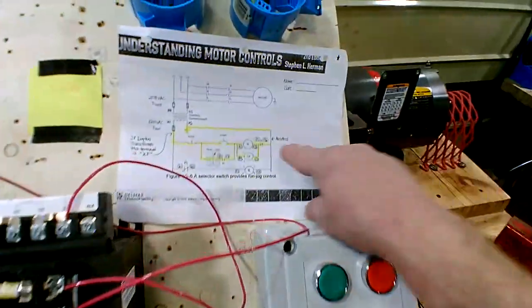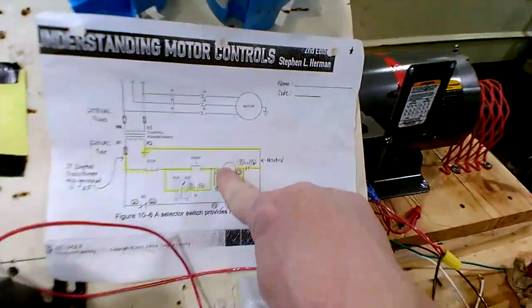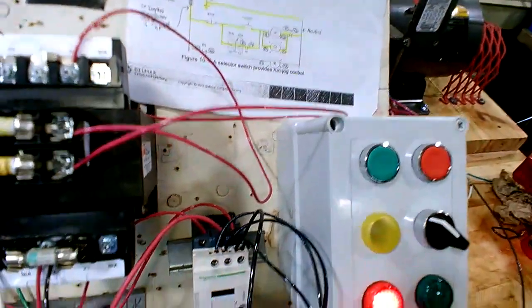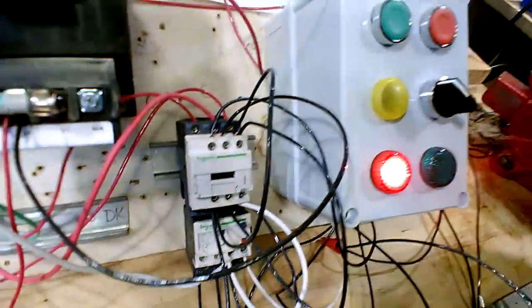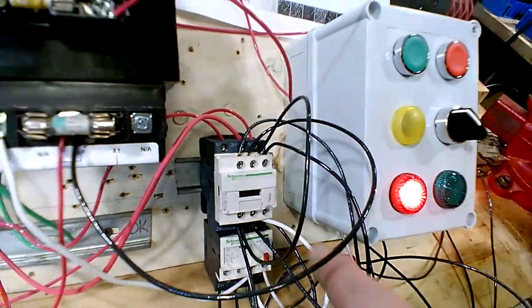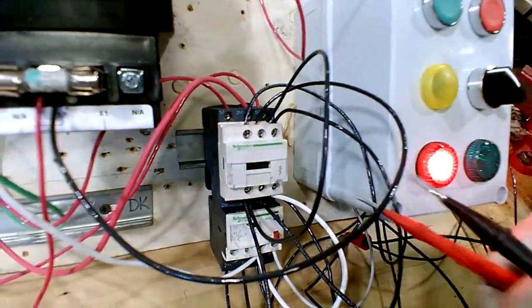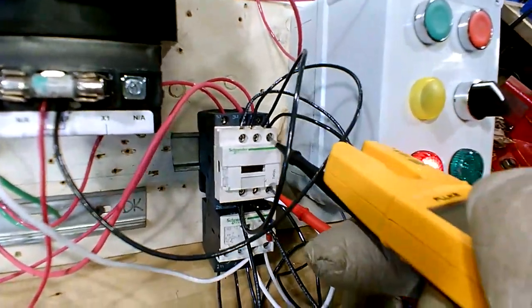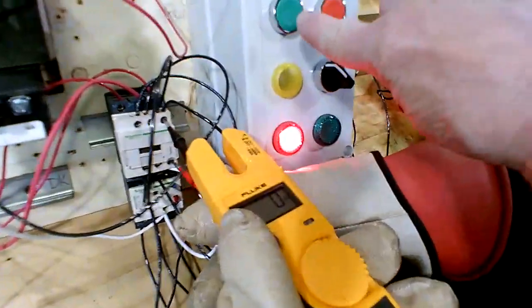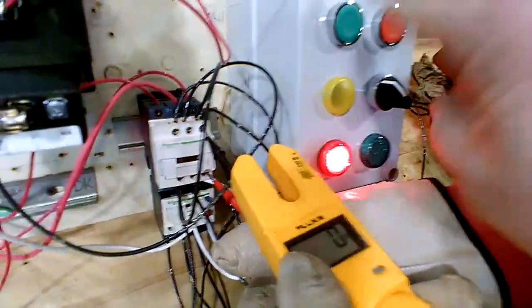And you actually could go across the coil, A1 and A2 there, and measure that and see, when I hold the button in, do you get voltage there. So if you go to the coil, your A1 and A2. Now I'm going to press the start button, and let's see what you get. You getting any voltage? Okay, none.